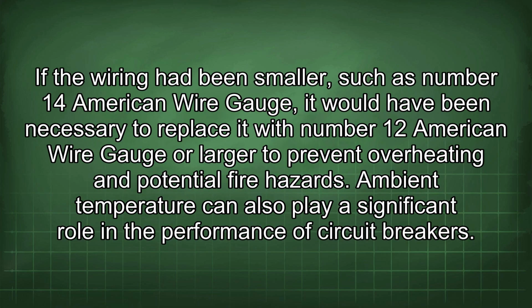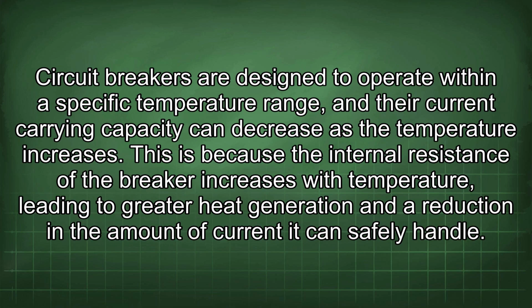If the wiring had been smaller, such as number 14 American wire gauge, it would have been necessary to replace it with number 12 American wire gauge or larger to prevent overheating and potential fire hazards. Ambient temperature can also play a significant role in the performance of circuit breakers. Circuit breakers are designed to operate within a specific temperature range, and their current carrying capacity can decrease as the temperature increases. This is because the internal resistance of the breaker increases with temperature, leading to greater heat generation and a reduction in the amount of current it can safely handle.